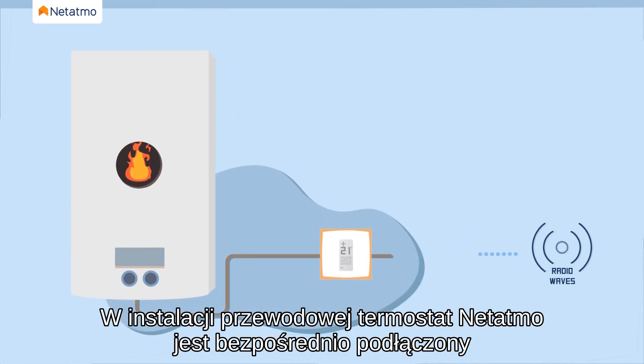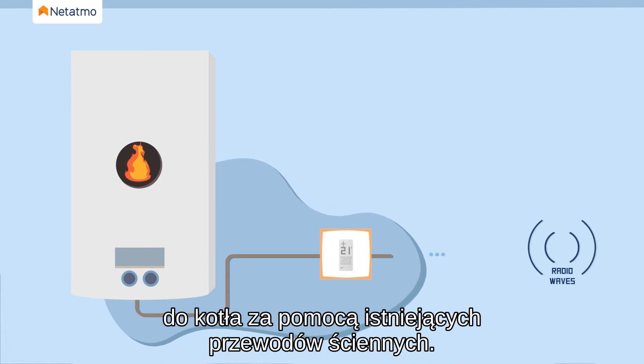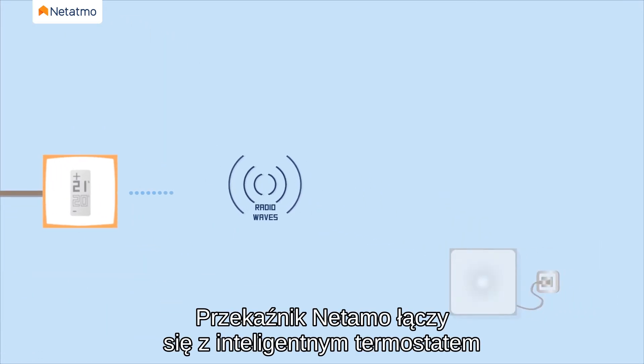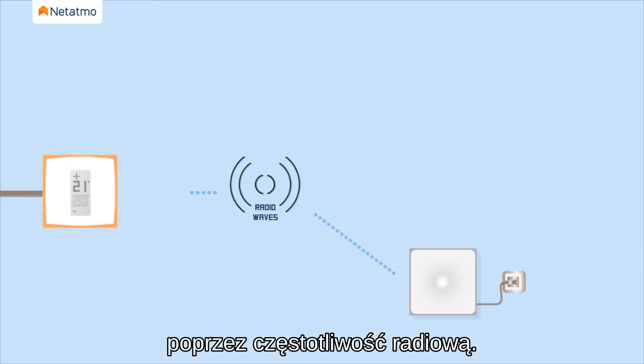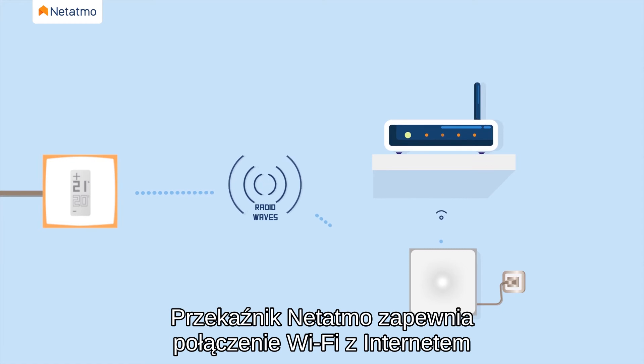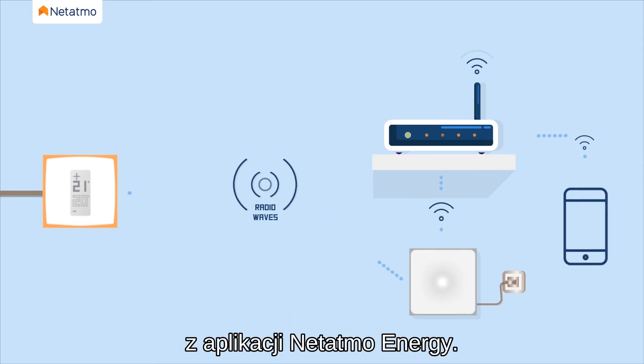In a wired installation, the Netatmo thermostat is directly linked to the boiler using the existing wall wires. Using a radio frequency, a wired smart thermostat connects to the Netatmo relay. The Netatmo relay ensures the Wi-Fi connection to the internet and the ability to remotely control the thermostat from the Netatmo energy app.